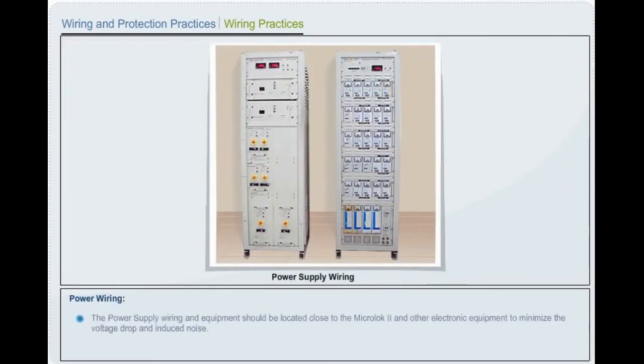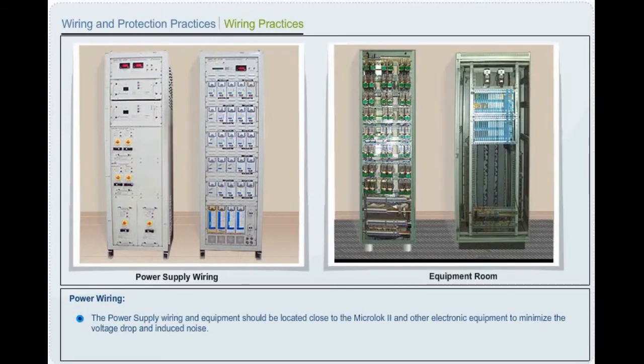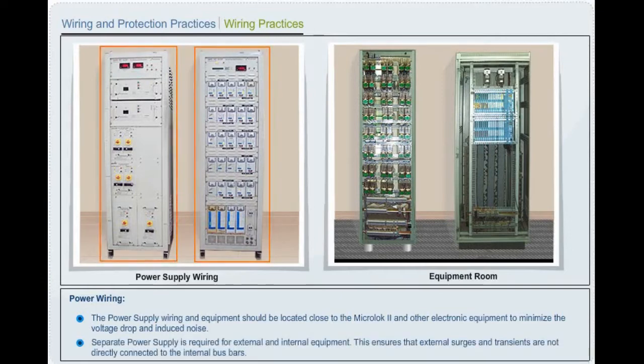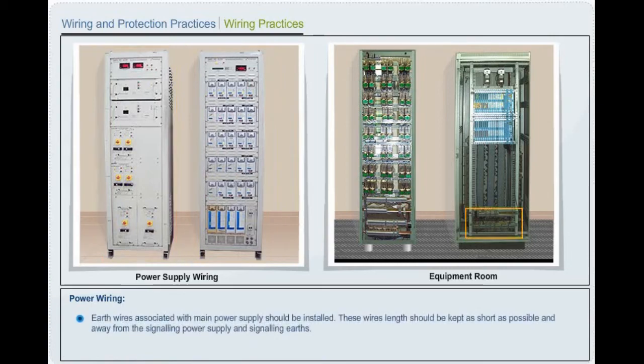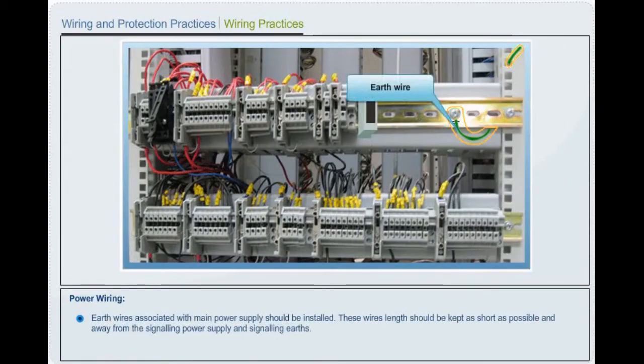Power wiring. The power supply wiring and equipment should be located close to the Microlok II and other electronic equipment to minimize the voltage drop and induced noise. Separate power supply is required for external and internal equipment. This ensures that external surges and transients are not directly connected to the internal bus bars. Earth wires associated with main power supply should be installed. These wire lengths should be kept as short as possible and away from the signaling power supply and signaling earths.